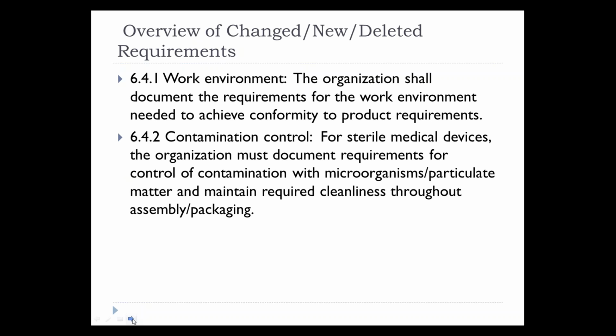6.4.1, work environment. You need to document the requirements for the work environment needed to achieve conformity to product requirements. Is a clean room necessary? Certain temperature, humidity, certain training, electrostatic discharge issues. 6.4.2, contamination control. If you're making a sterile medical device, you need to document requirements for controlling contamination with microorganisms or particulate matter and maintaining required cleanliness throughout assembly and packaging.